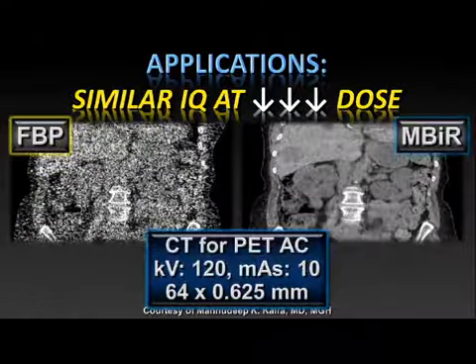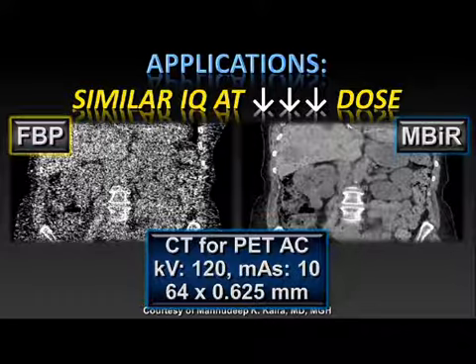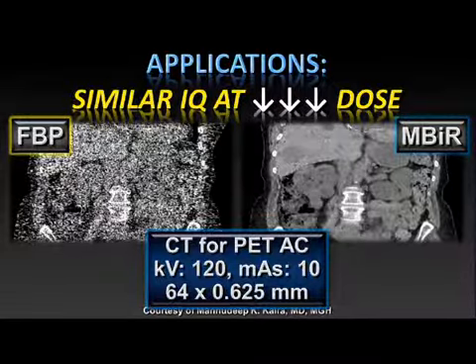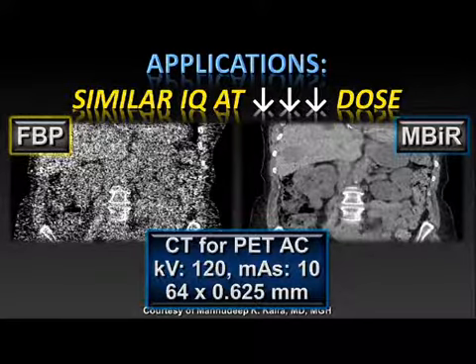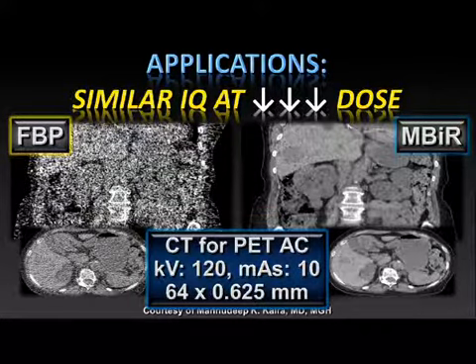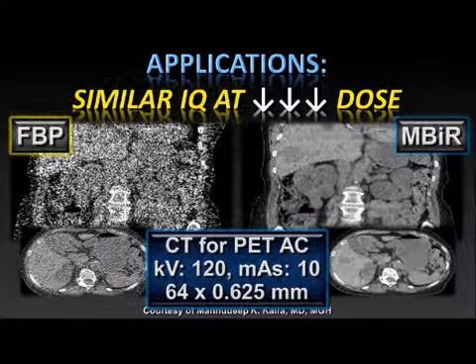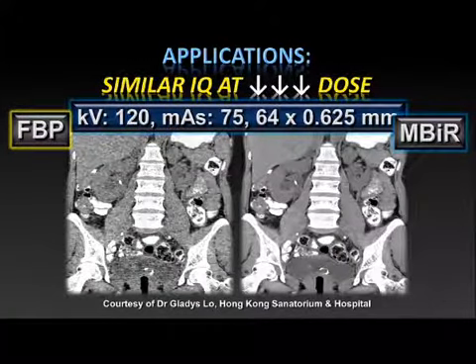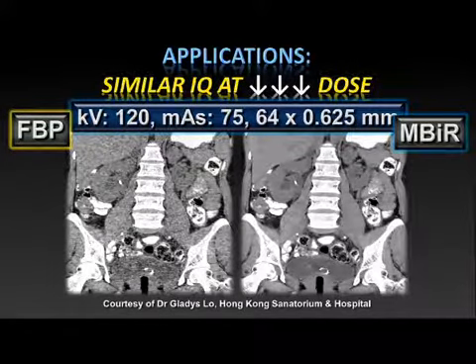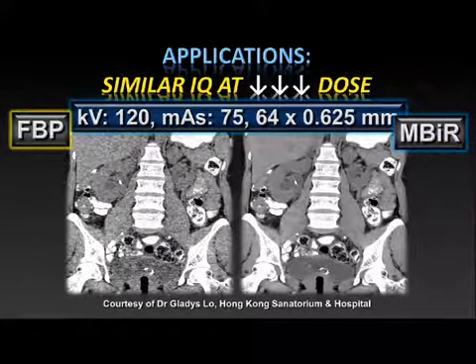Here's one from Dr. Kalra. This is an attenuation-corrected image from PET — a terrible image using filtered back-projection, but with MBIR on the right, at least in terms of attenuation correction, you have a much better image, albeit far from perfect. That was a remarkably low-dose technique at an MAS of only 10. Here's another example: filtered back-projected on the left, iterative reconstruction on the right, MAS of 75, with a nice increase in image quality with iterative reconstruction.